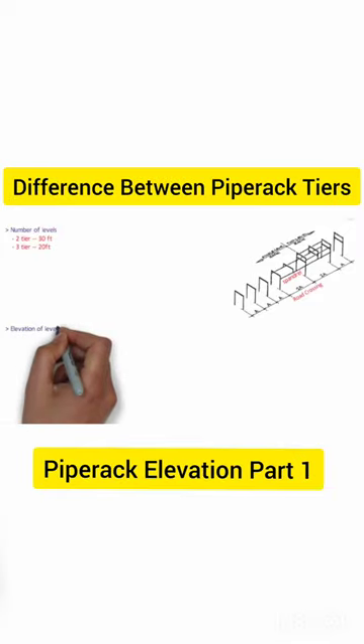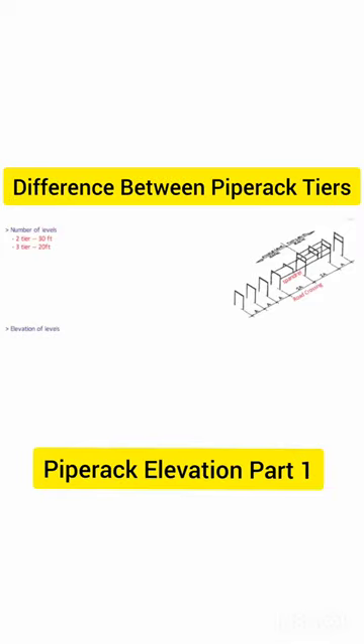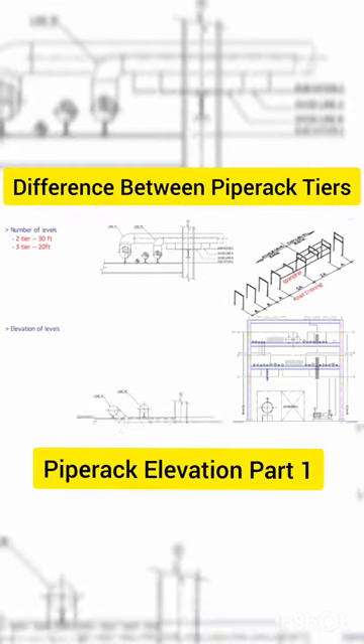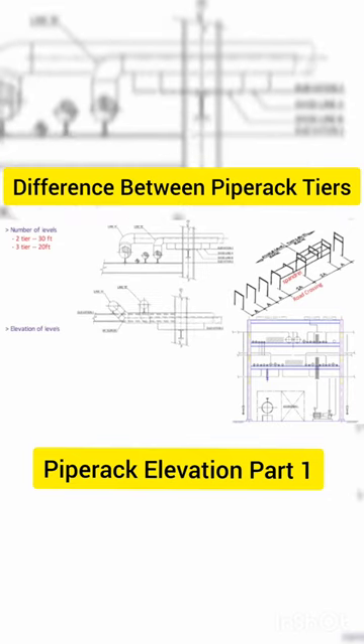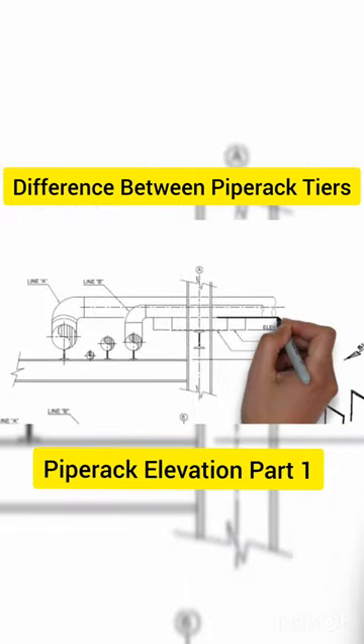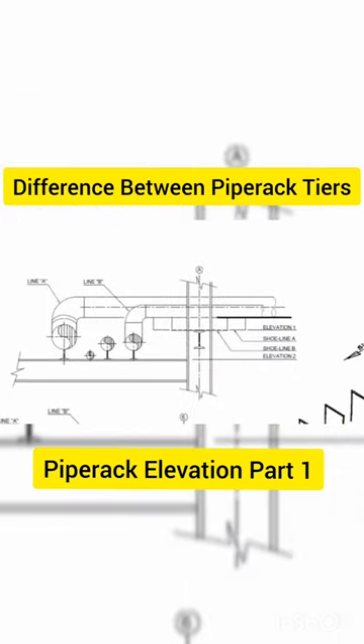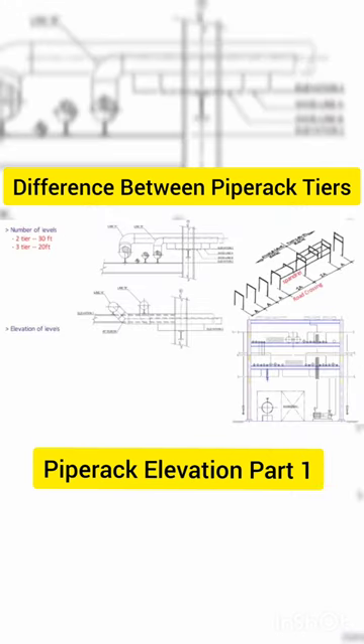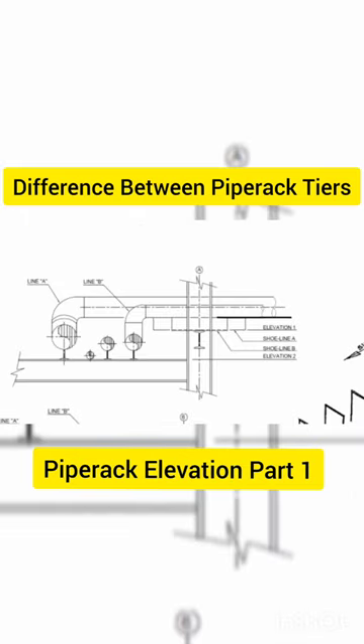First, we will see the gap between the tiers. It shall be decided on the basis of the largest diameter pipeline and its branching. The difference between the bottom line of pipe in the rack and the bottom of branch as it leaves the rack shall be decided carefully to avoid any interference due to support, insulation, size of branch, etc.